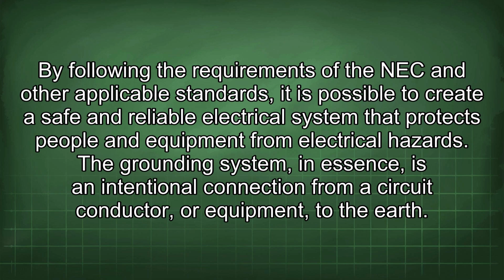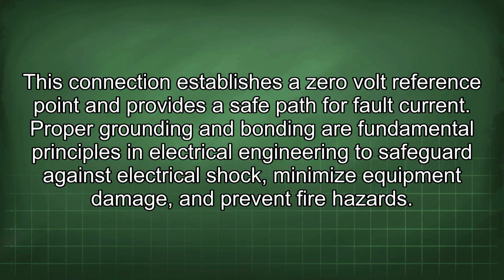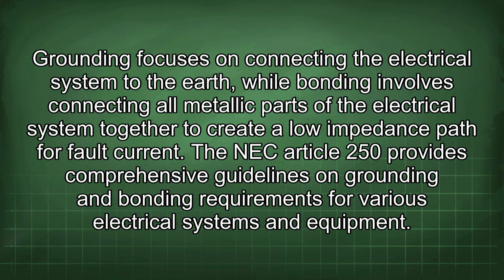The grounding system, in essence, is an intentional connection from a circuit conductor or equipment to the earth. This connection establishes a 0-volt reference point and provides a safe path for fault current. Proper grounding and bonding are fundamental principles in electrical engineering to safeguard against electrical shock, minimize equipment damage, and prevent fire hazards. Grounding focuses on connecting the electrical system to the earth, while bonding involves connecting all metallic parts of the electrical system together to create a low impedance path for fault current.